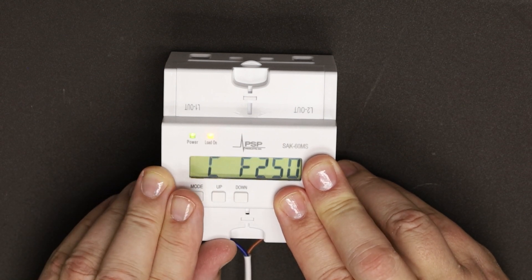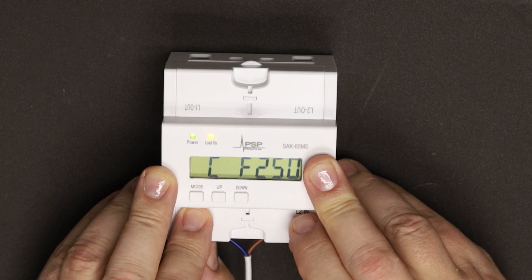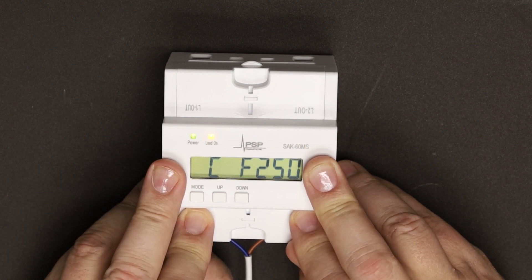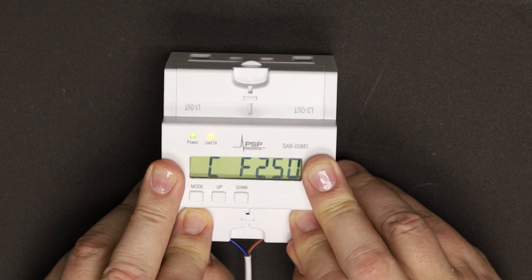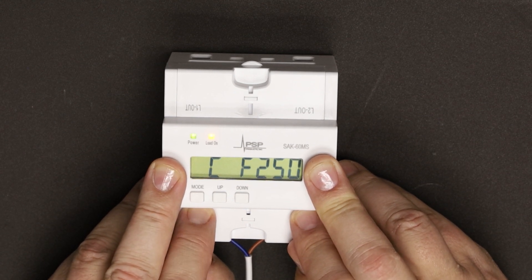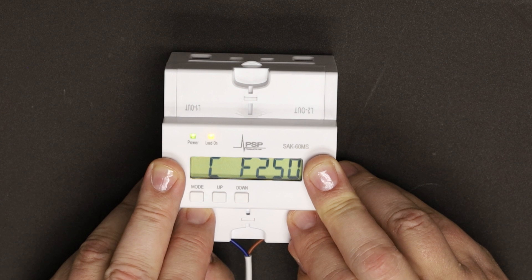The first setting, CF, is the CT full current range. That's the maximum ampacity that the CT is capable of reading. It is not the maximum panel ampacity. We ship these standard with 250-amp CTs, so CF should be set to 250.